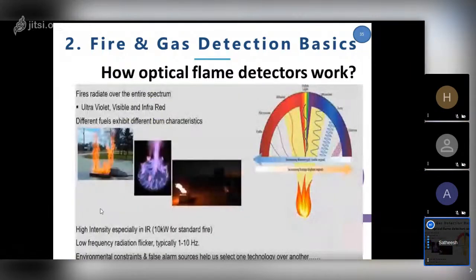All these optical flame detectors look for specific radiation coming out of the fire. For example, the UV detector looks at this range of the spectra, whereas infrared looks at a different range, and each fuel burns differently. So there's a challenge—we need to select the flame detector accordingly to catch the fires.